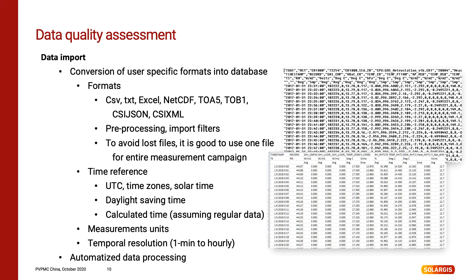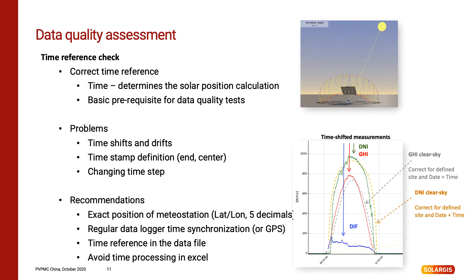From our side we prefer minute or sub-hourly temporal resolution, and time reference is important for further processing. Next, we need to do a time reference check. Solar irradiation is dependent on the position of the Sun, so we need to know the exact time for further data quality tests. Issues include time shifts and drift, unclear timestamp definition or changing timestep. To avoid these problems, exact site coordinates are needed with at least five decimal points. It is recommended to perform regular data logger time synchronization or use a GPS receiver to make sure you have correct data logger timestamps. It is good practice to record timestamps together with measured data, and it is important to avoid time processing in tools such as Excel. Also, combining measurements from several meteostations with different time references is not a good practice.